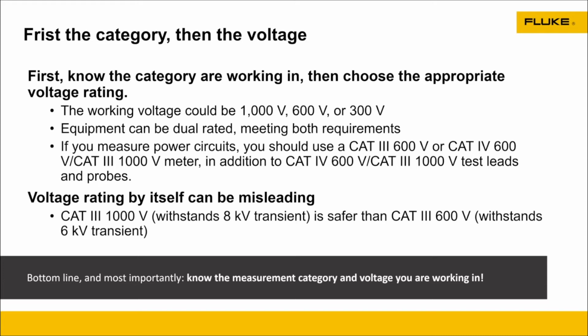You're going to see that on the meter. Hopefully it's going to display it because you know exactly where you're working. When I was out in the field working as an HVAC guy, it was typically 120 volts or it was 240 volts. There were times I would get into 480. You're up on a rooftop working on a package unit up there. But again, you kind of understand where you're at. But knowing that category rating is really critical.